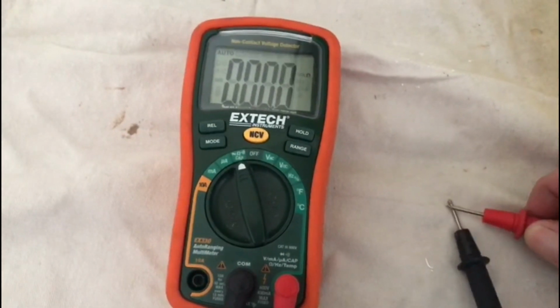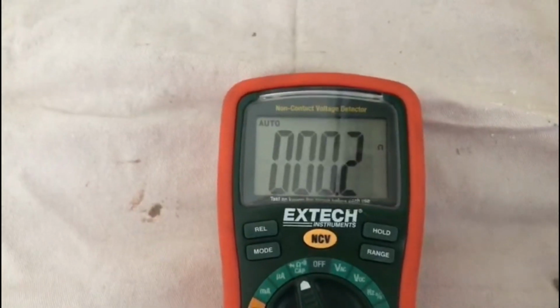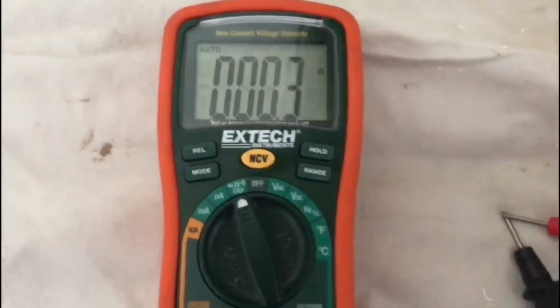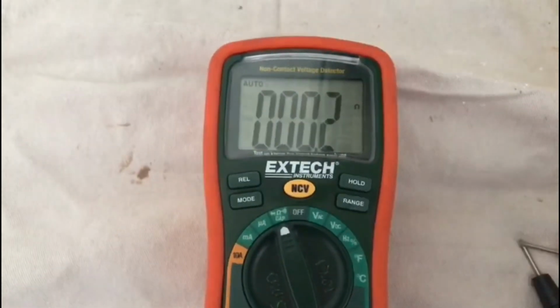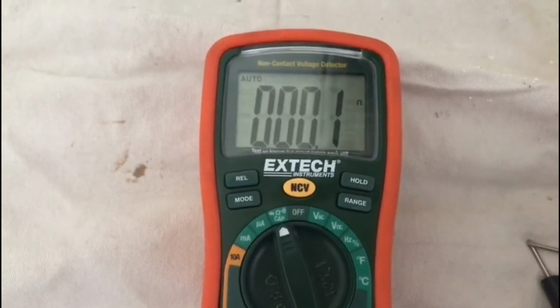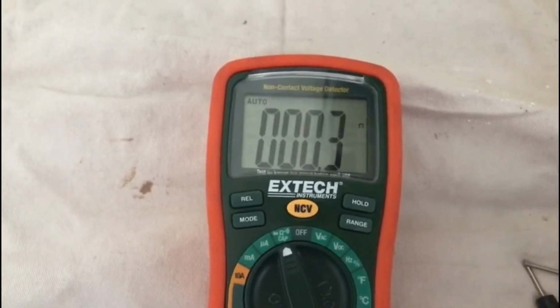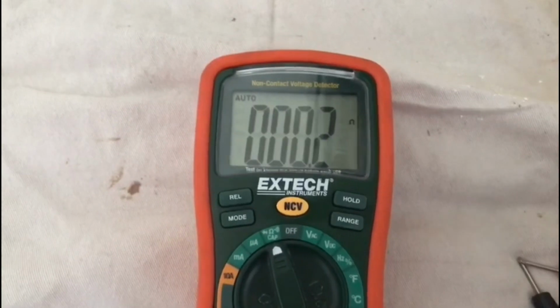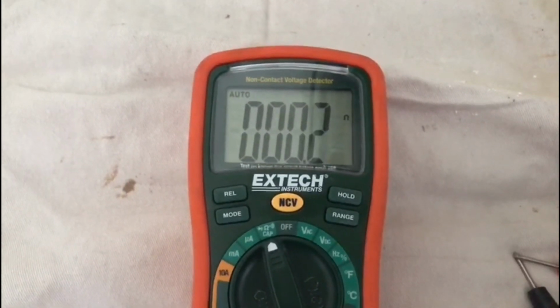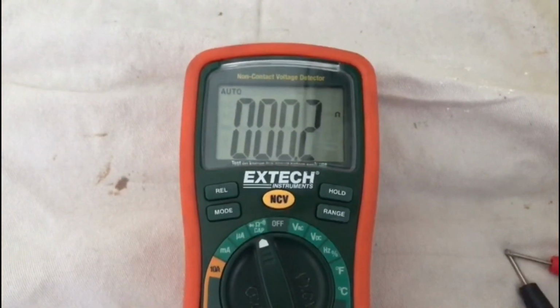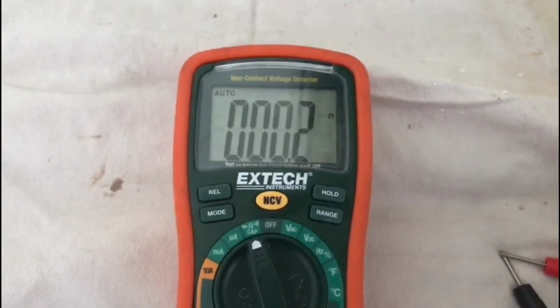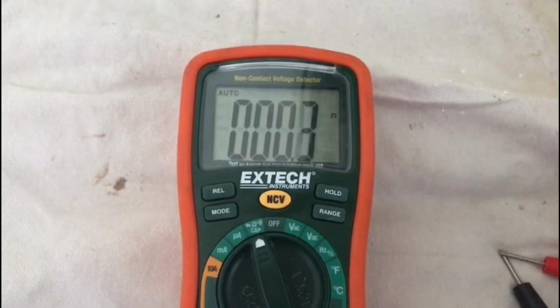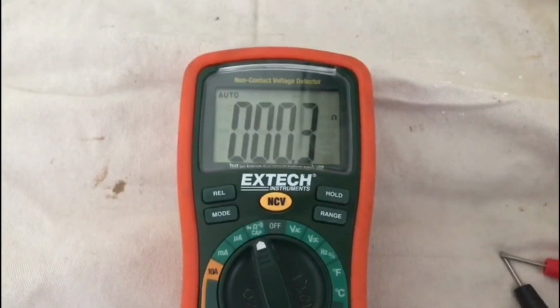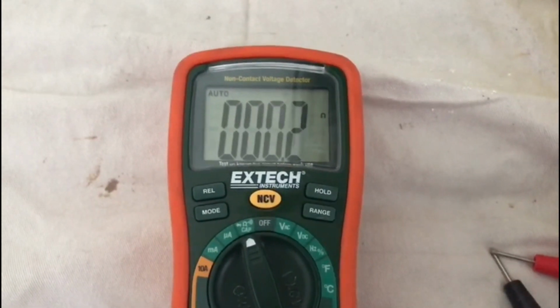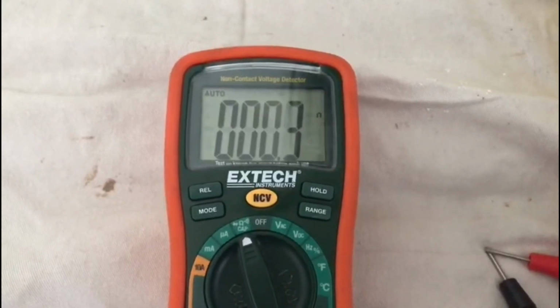Test your 2 probes together. You should get a resistance reading of the fuses inside your multimeter. That's them both touching there, getting a reading of 0.2 ohms. So that just tells me the resistance of my fuses. So when I do my test, and if everything's okay and I've got continuity, in other words there's a link between them both, then I know that I'm safe to work. Especially with earth continuity, if you're testing your earth from your boiler to the earth of your whole house system, and you're getting anything other than continuity, there could be a short circuit somewhere. A short circuit could lead to, obviously, electrical problems, cause it to trip, lots of different things. So we'll test earth continuity next. Earth continuity testing.